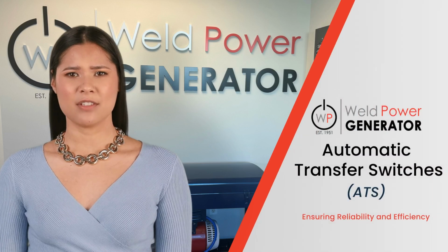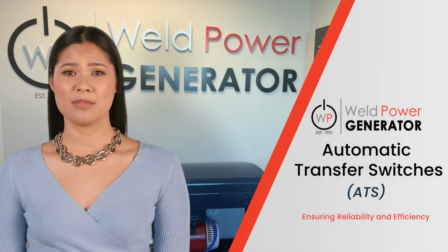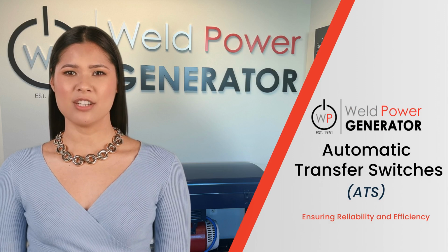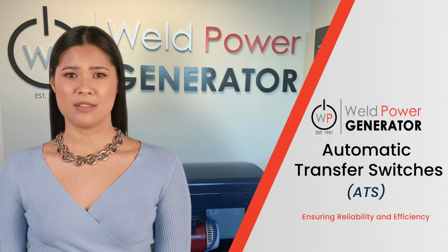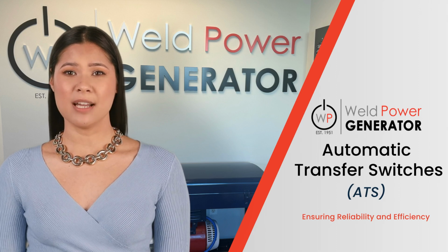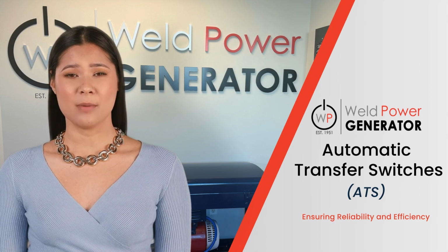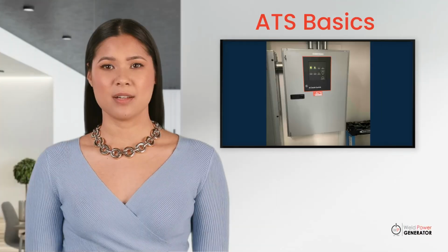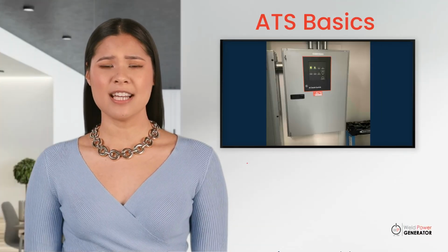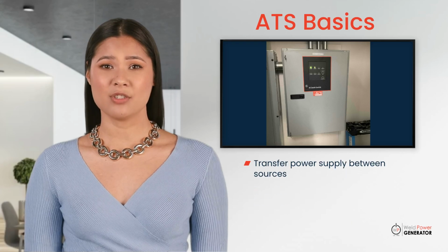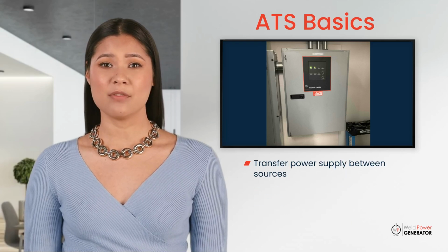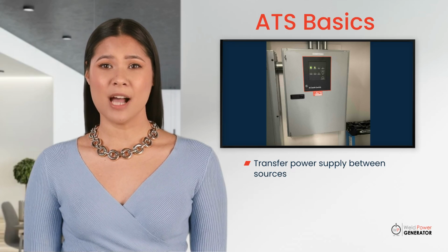An automatic transfer switch, or an ATS, is the backbone of reliable power systems, especially in industries where downtime is not an option. Let's dive into the world of automatic transfer switches, exploring their function, importance, maintenance needs, and common issues. A transfer switch is a device that transfers the power supply from the primary source, typically the utility provider, to a backup generator during a power outage.